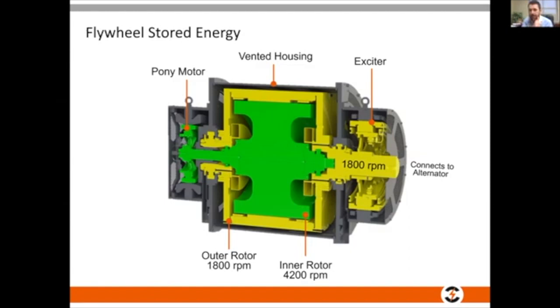And to get a little bit deeper, this is how we do it. So, you know that we mechanically couple a flywheel to the end of the diesel generator. So I'm not showing you the diesel generator here. The end of the alternator is here. Now, a standard diesel generator has the exciter and everything mounted on the end. We don't do that. We actually have an open end. We have the end of the shaft open to us, and we connect a flange. And so what we do first and foremost is we connect this shaft to the alternator shaft via that flange.